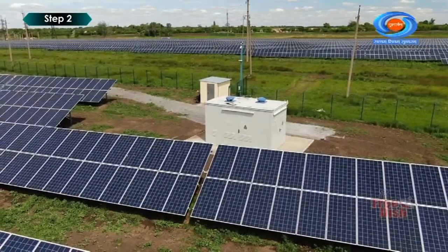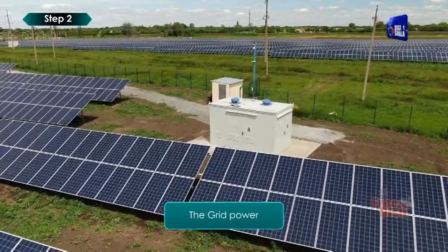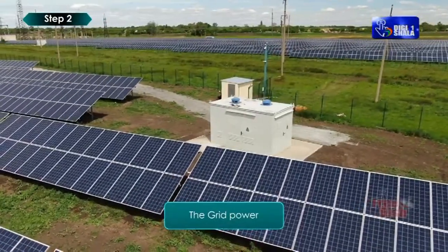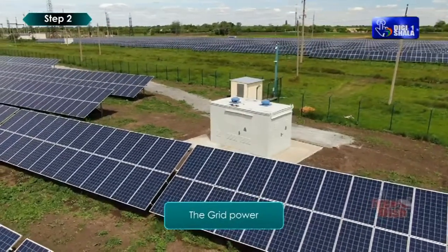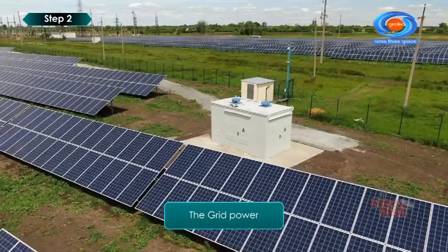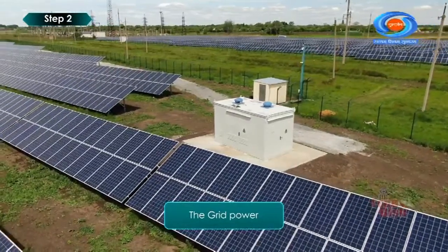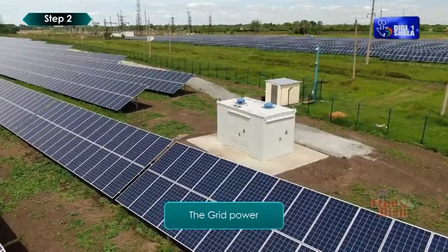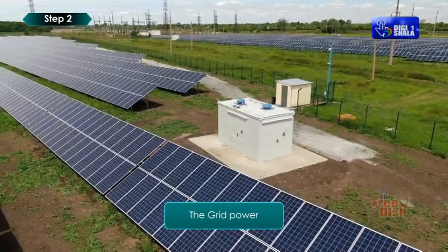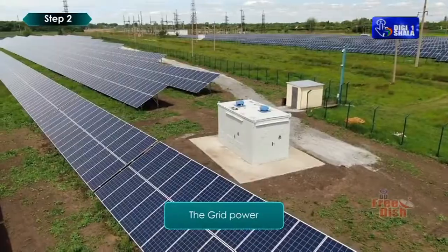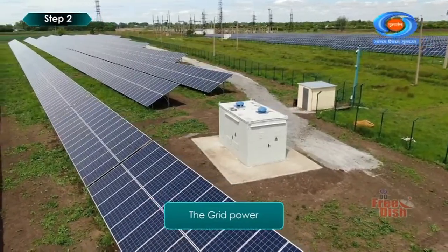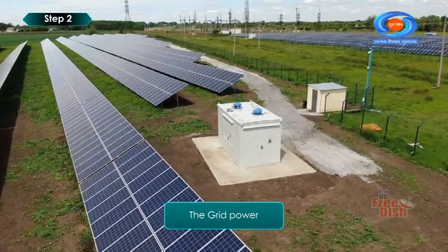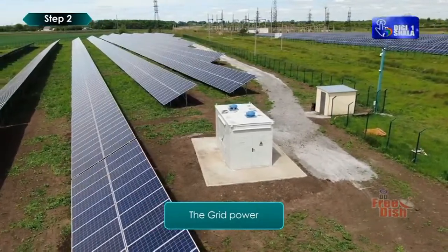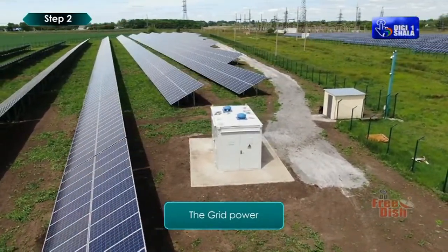Distribution panel to grid connections. The grid power is in the form of AC, and if we need to supply power to the grid, we need the output of solar plants to be similar to the power of the grid. In this system, the most important condition is that the output frequency and voltage must be matched with the grid's frequency and voltage, and also the power quality maintains the grid standard.